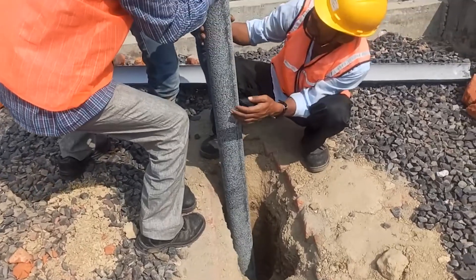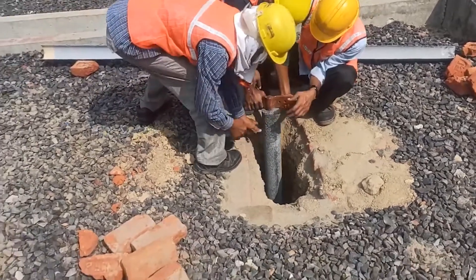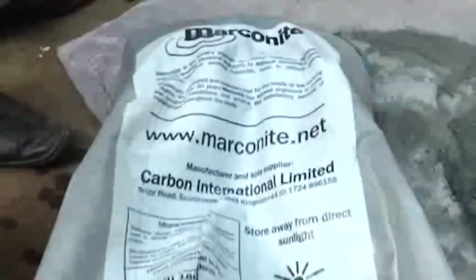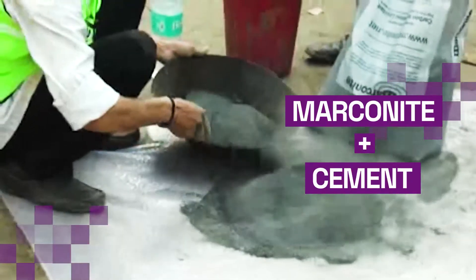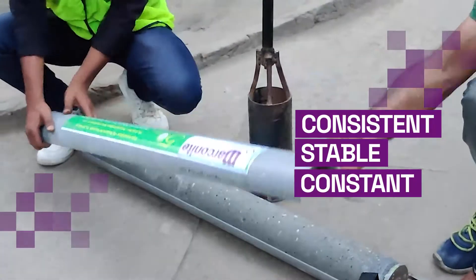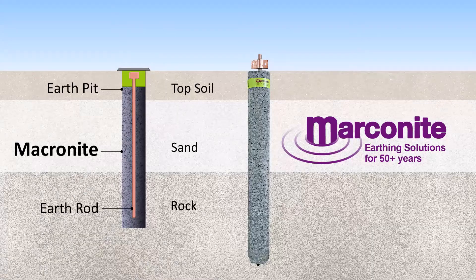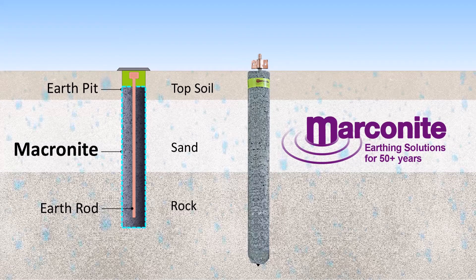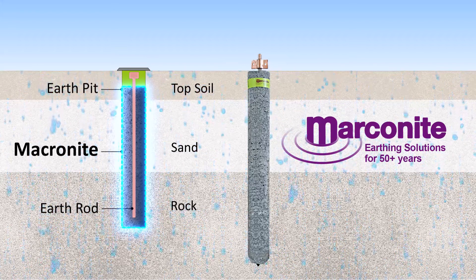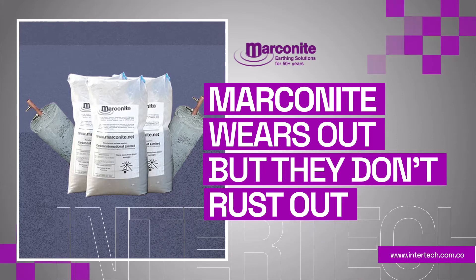The solution lies in adopting corrosion-less technology to strengthen our earth pits for more consistent performance. One such revolutionary technology in the earthing industry is mixing cement and Marconite, which is able to conduct persistent, stable, and constant performance without any need of moisture. In addition, conductive concrete around the metal conductor prevents ingress of moisture by creating a protective layer around the conductor. Earthing structures with Marconite wear out — they don't rust out.